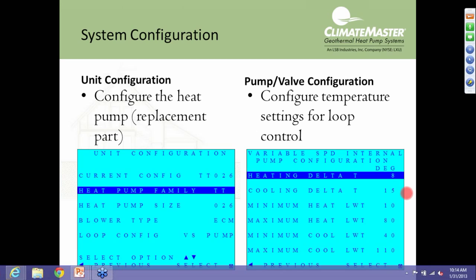The next item is the blower type. This is where you'll choose, again, ECM motor, PSC motor, or the blower type will be none. It'll say none there on the DXM2 if you're doing a split, because on the DXM2 there is no blower attached directly to it. It'll be part of the AXM board in the split system.